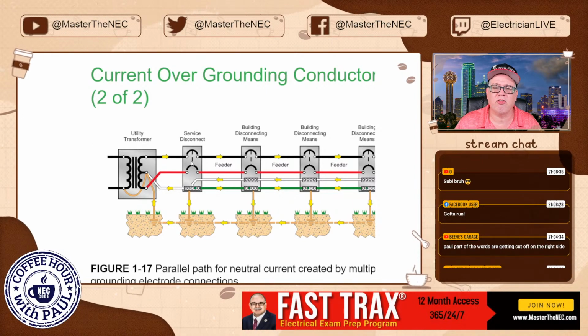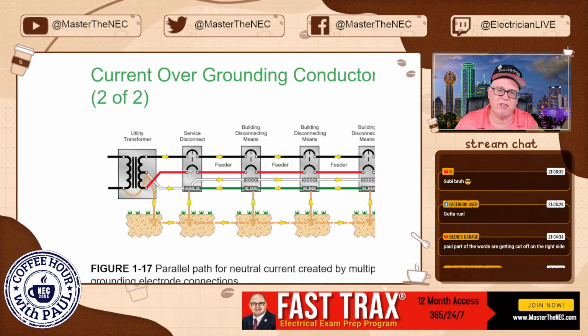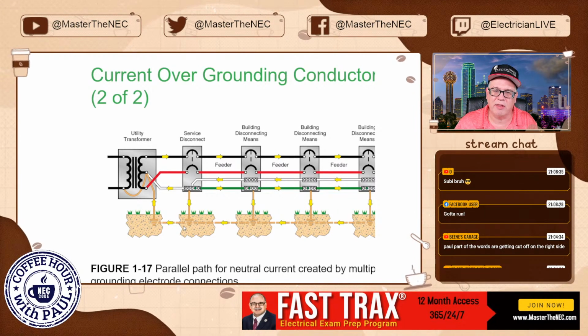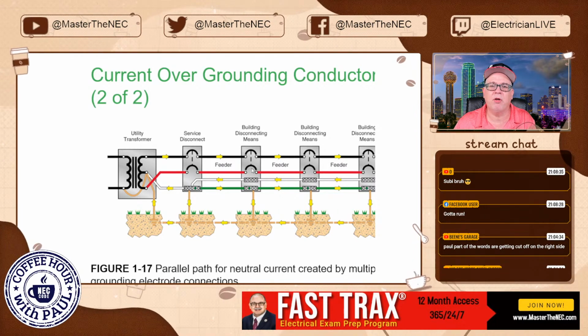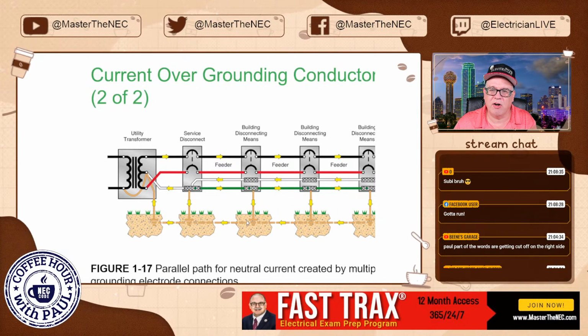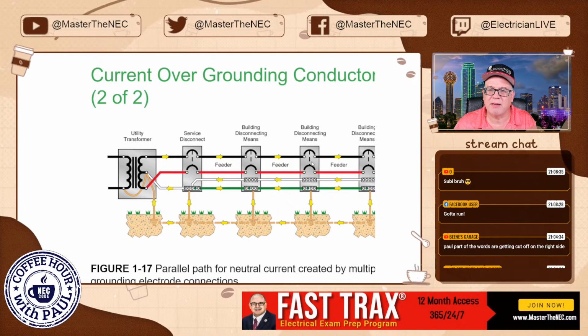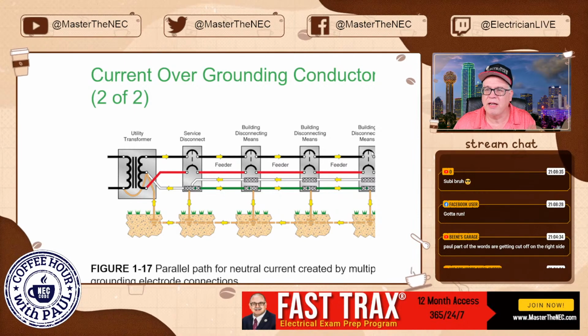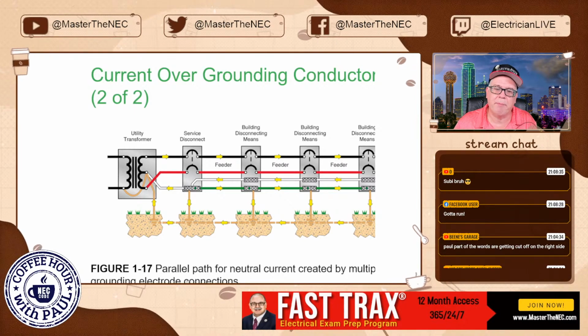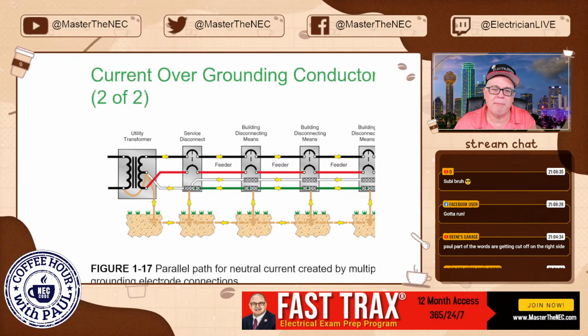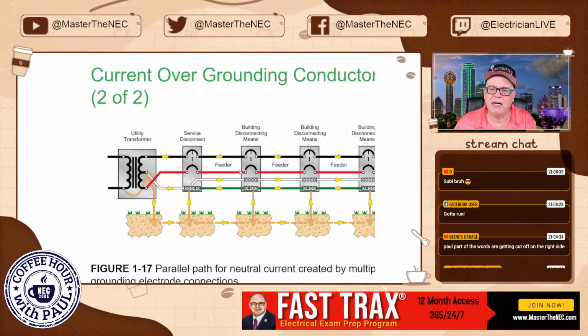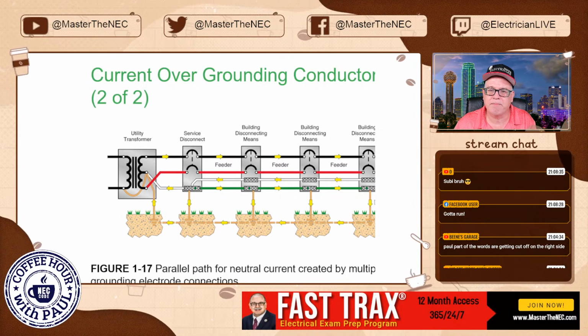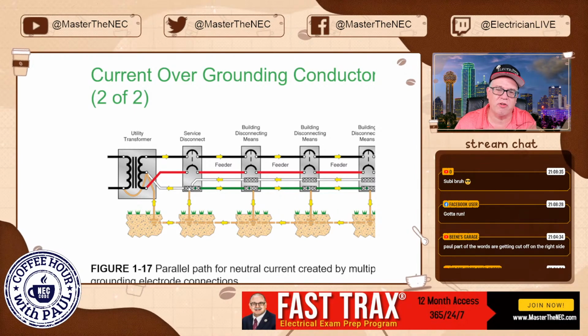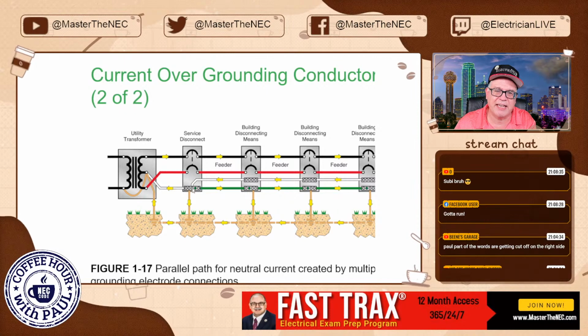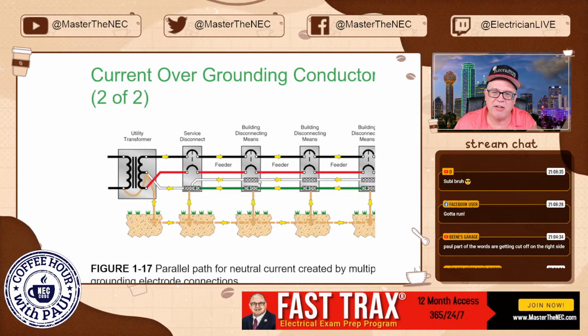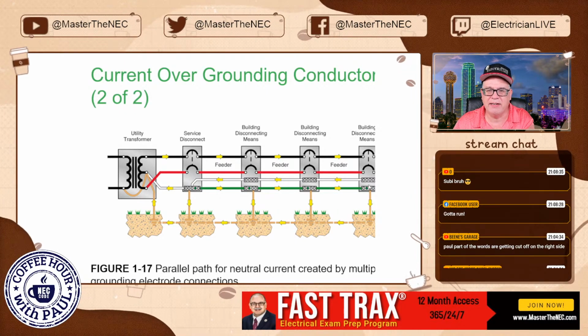All right, so anyway, here's the service. Now it goes downstream. So here's the service, and it has to have a connection to earth, okay? Now here, the building's main disconnect, connected to earth again. Then the building's disconnect to meet another feeder, connected to earth, and then another one connected to earth. So you've got parallel paths for neutral current created by multiple grounding electrode connections. I remind you that you'll notice that together here, they're together on one bus, but as they get downstream, they're isolated, okay?